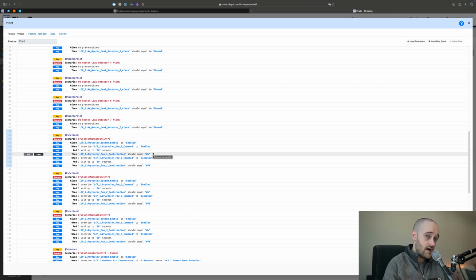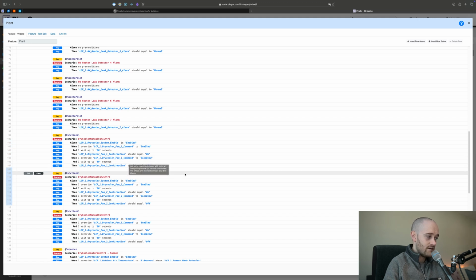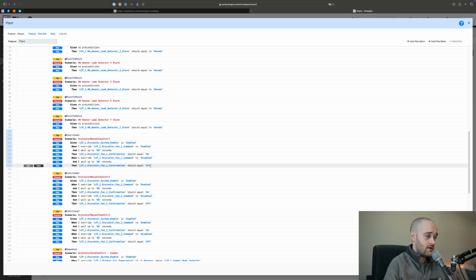If it's okay, obviously we're succeeding. And then we're going to override the fan command to disabled, wait, and then we're going to expect to see that our status on that is off. If it's off, then we succeed that test. If it's not off, then we've obviously failed.